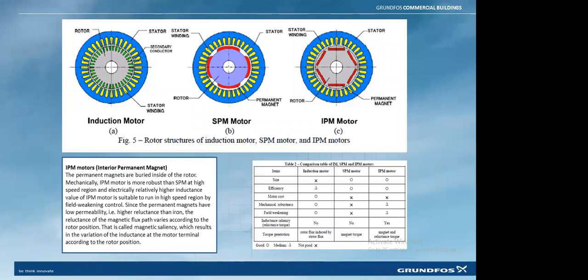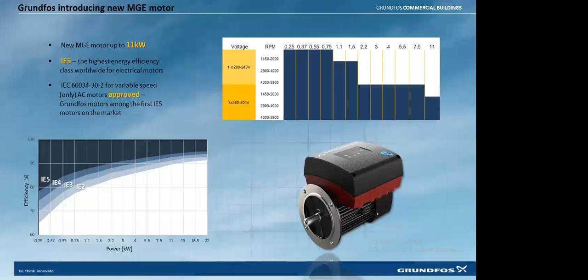Of course, we made a comparison on some key factors like size, efficiency, motor cost, mechanical robustness, field weakening and torque generation. Normally the IE5 permanent magnet motor performs better than our induction motor concept. Can you go to the next one? So in Grundfos, we have come up with that IE5 motor, and we developed it up to 11 kilowatt.